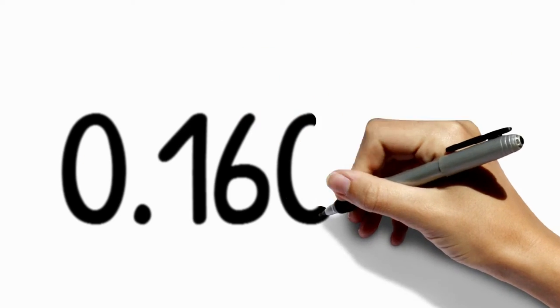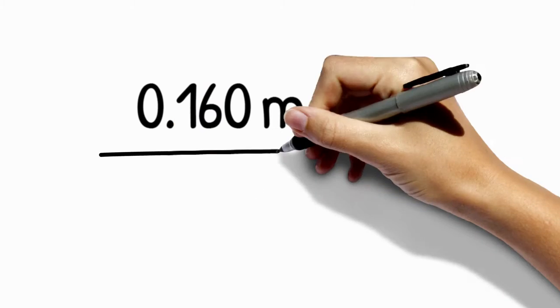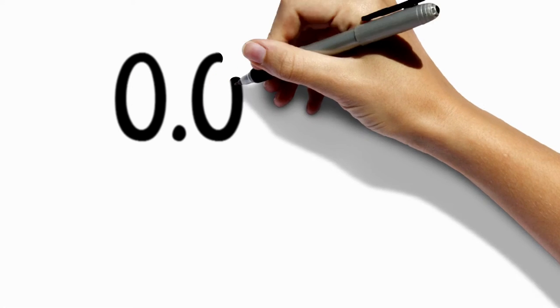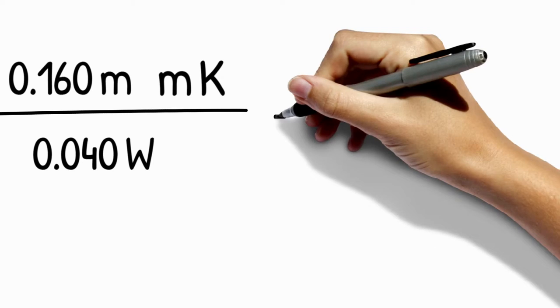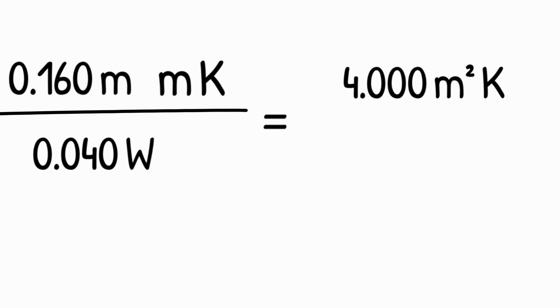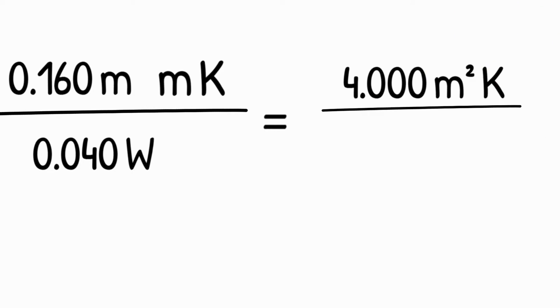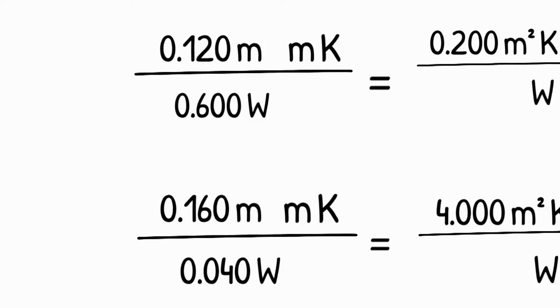Add a layer of insulation in 0.16 meters thickness and put this over the thermal conductivity of this insulation material, which is 0.04 watt per meter kelvin, and we get a resistance of this layer of 4.0 square meter kelvin over watt.